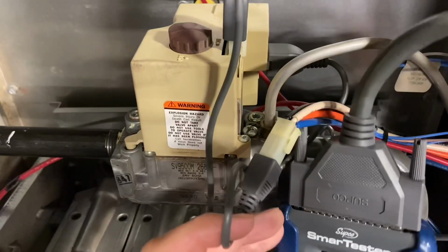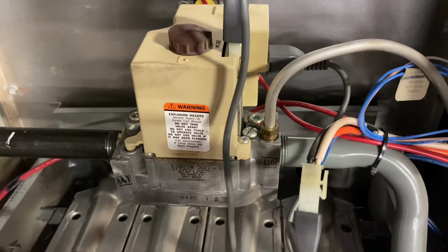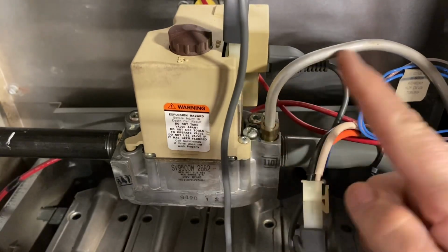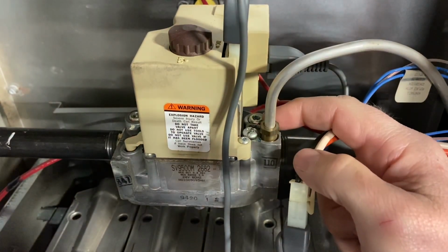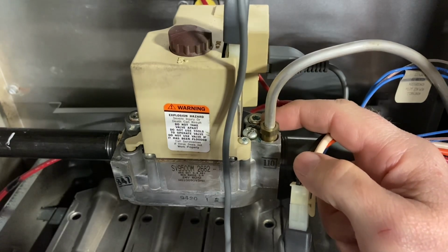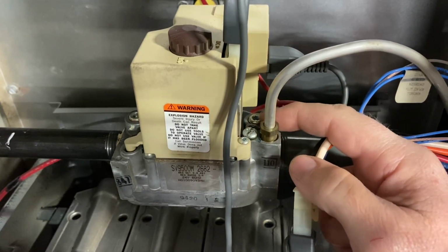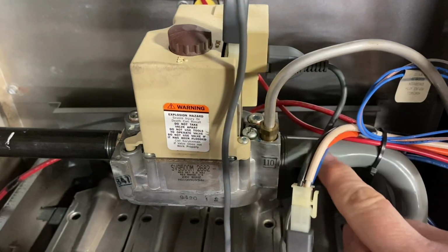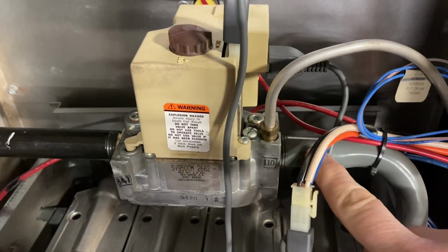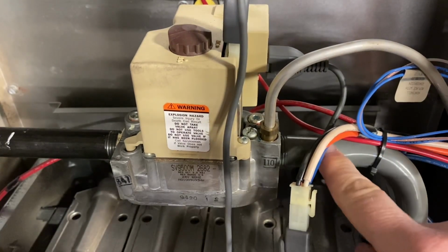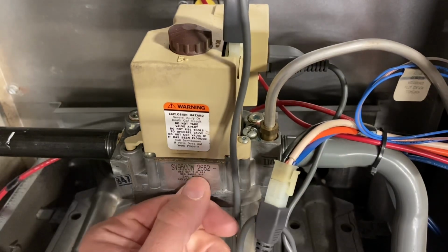On the other side, we're going to move our little meter out of the way. You can see our pilot tube that's coming out, as well as we have another port right here. This port is going to be for our manifold pressure. We take that port out, we can put an adapter in there and read the manifold pressure.